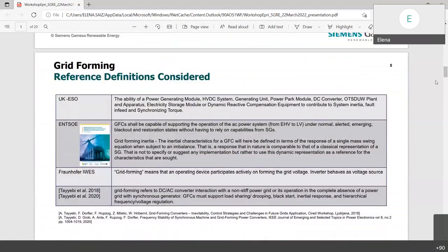We have already discussed in several presentations by now, and we still don't have a common definition of grid forming. If we check different sources, we can identify that there are slightly different understandings of what grid forming is. In all cases, it is the ability of any generation unit to contribute to the system inertia, fault feed, and also synchronizing torque. However, in some places black start is also put as a service associated to the grid forming. As other commenters have already said, we should really decouple the grid forming capability from black start.